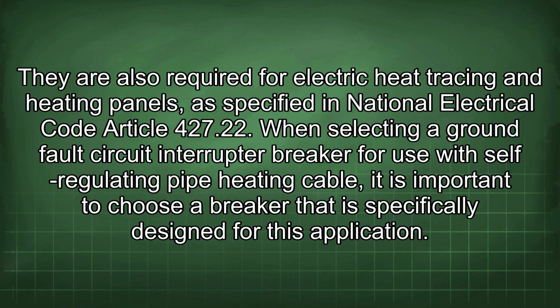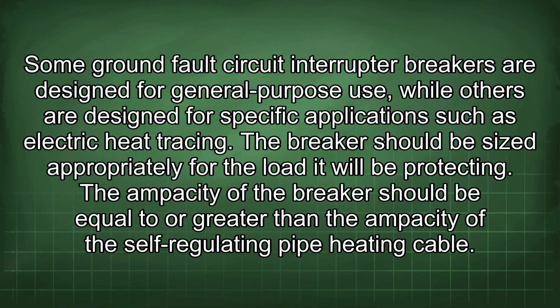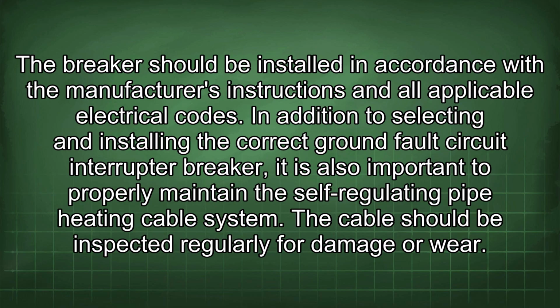When selecting a ground fault circuit interrupter breaker for use with self-regulating pipe heating cable, it is important to choose a breaker that is specifically designed for this application. Some ground fault circuit interrupter breakers are designed for general purpose use, while others are designed for specific applications such as electric heat tracing. The breaker should be sized appropriately for the load it will be protecting. The ampacity of the breaker should be equal to or greater than the ampacity of the self-regulating pipe heating cable. The breaker should be installed in accordance with the manufacturer's instructions and all applicable electrical codes.